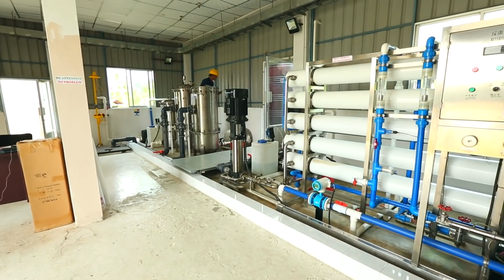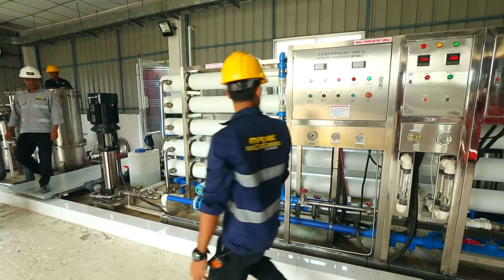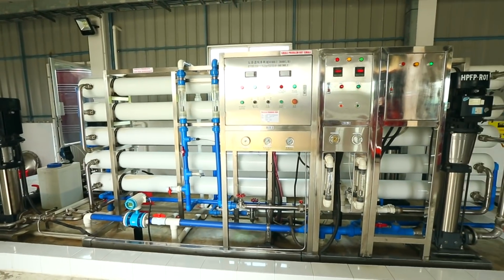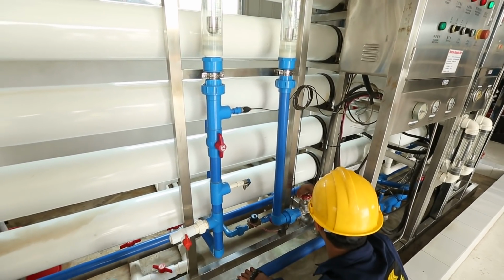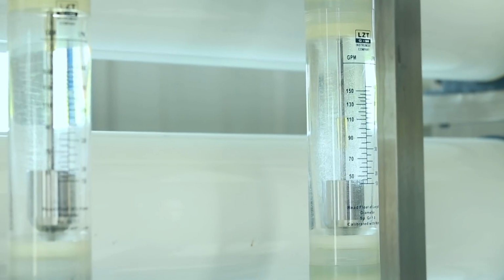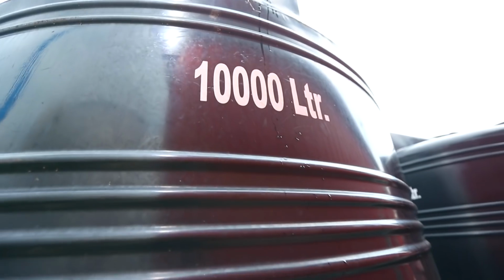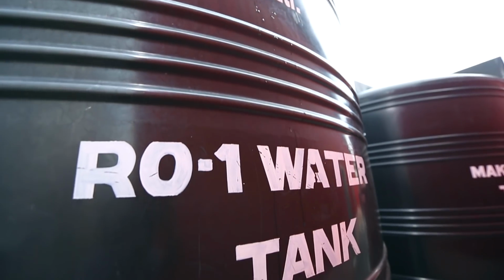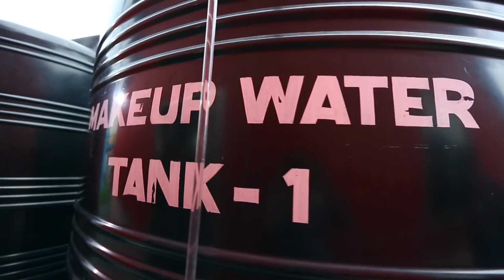Water after RO stage 1 is demineralized to about 98 to 99%, and on further passing through RO stage 2 attains the desired purity level. It is stored in 2 demineralized water storage tanks and is delivered to the feed tanks of the GT unit.